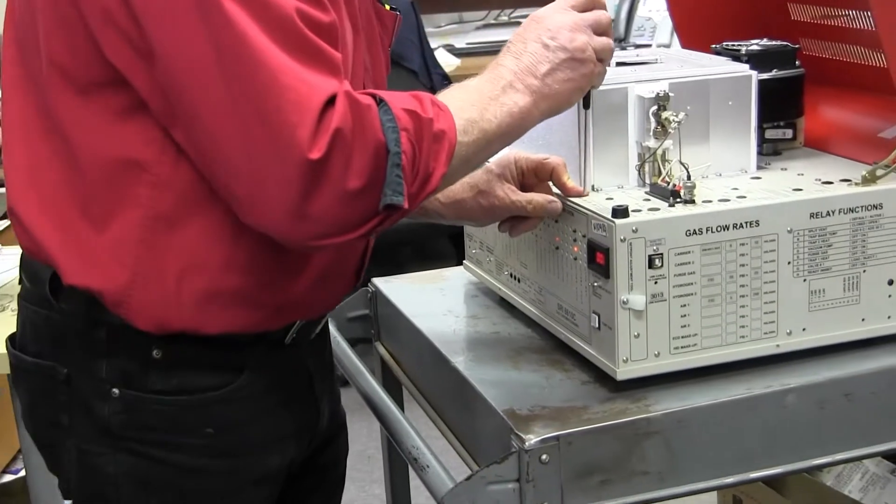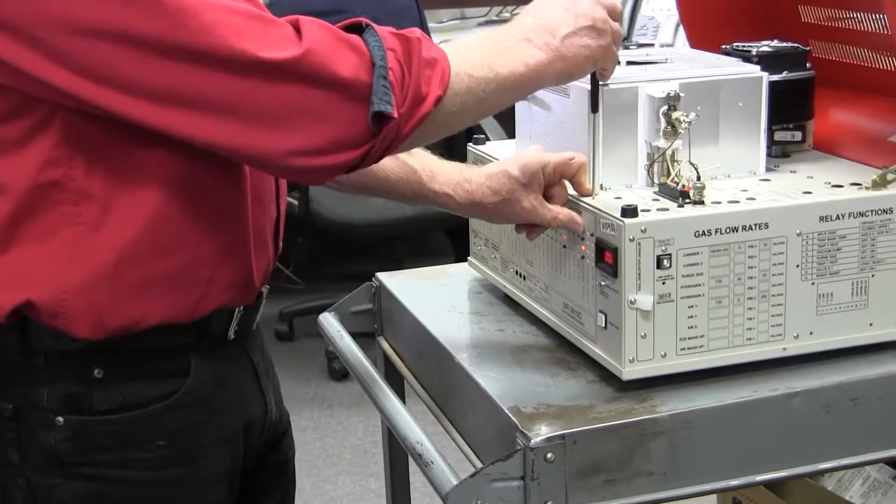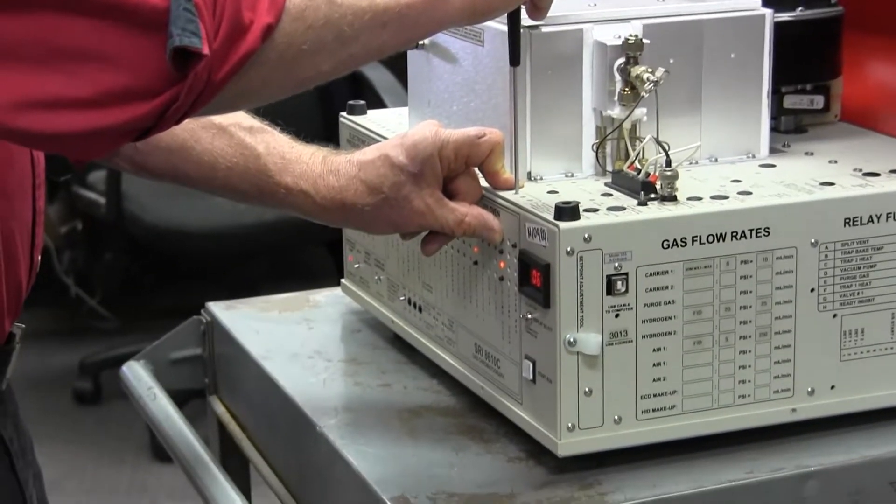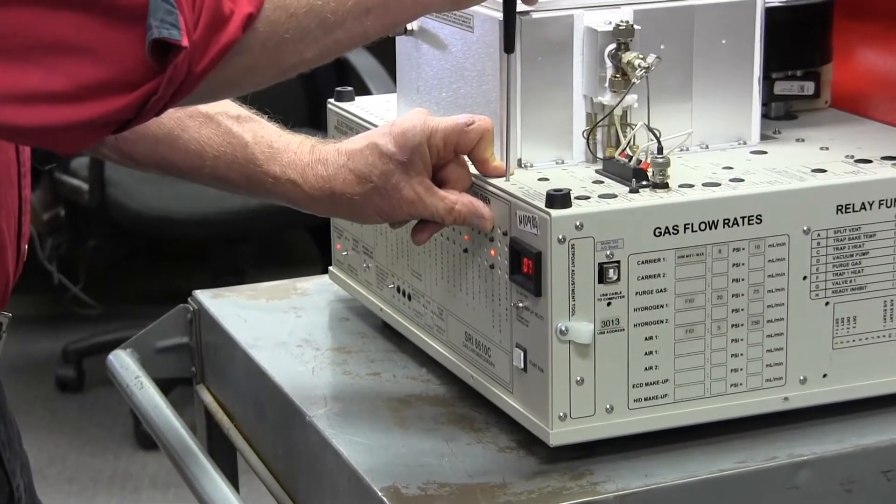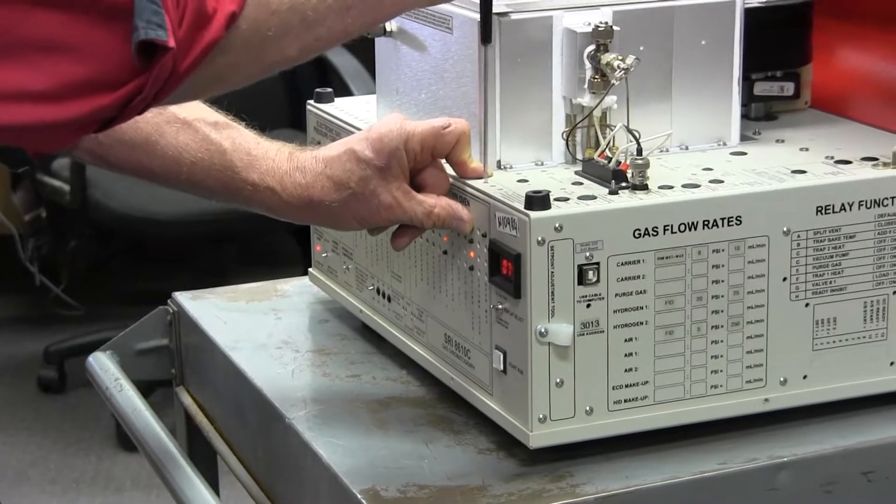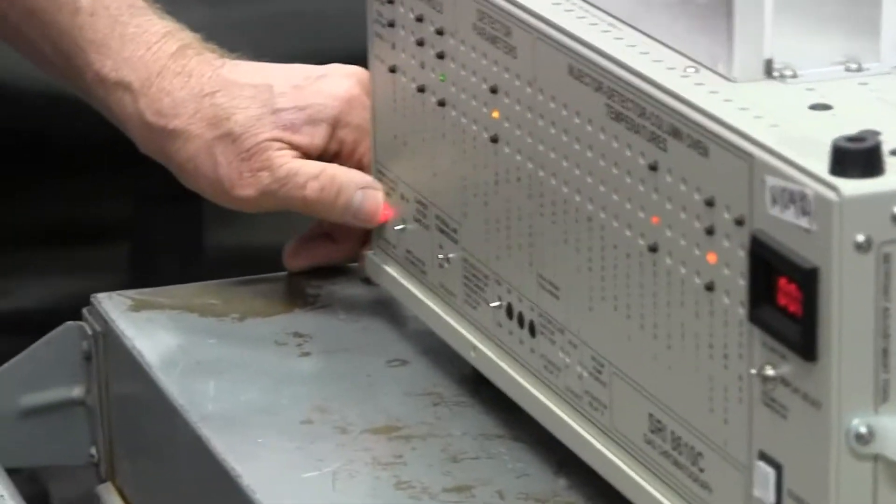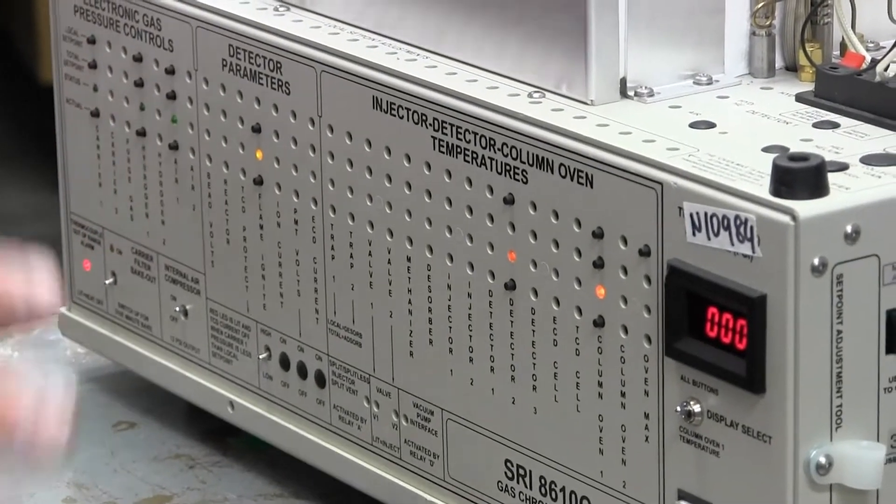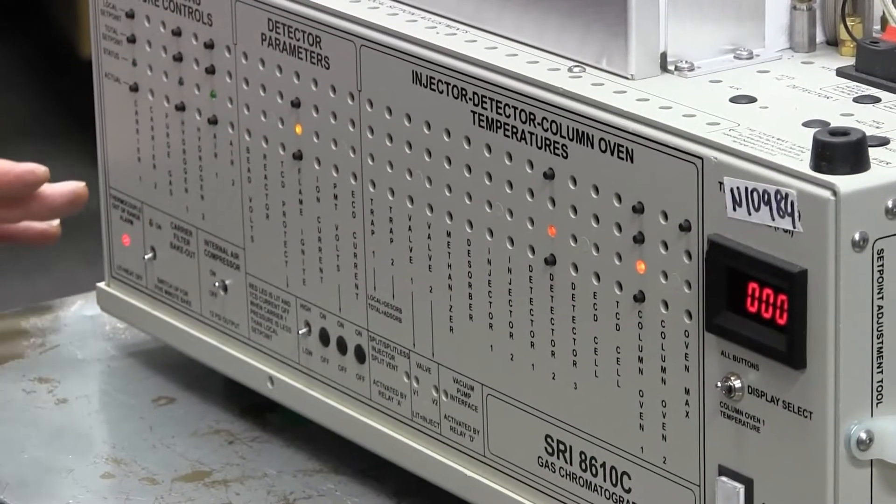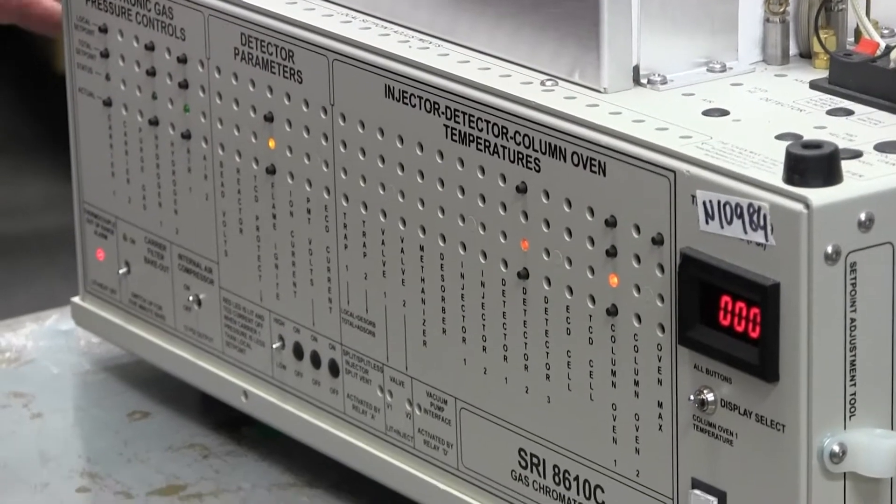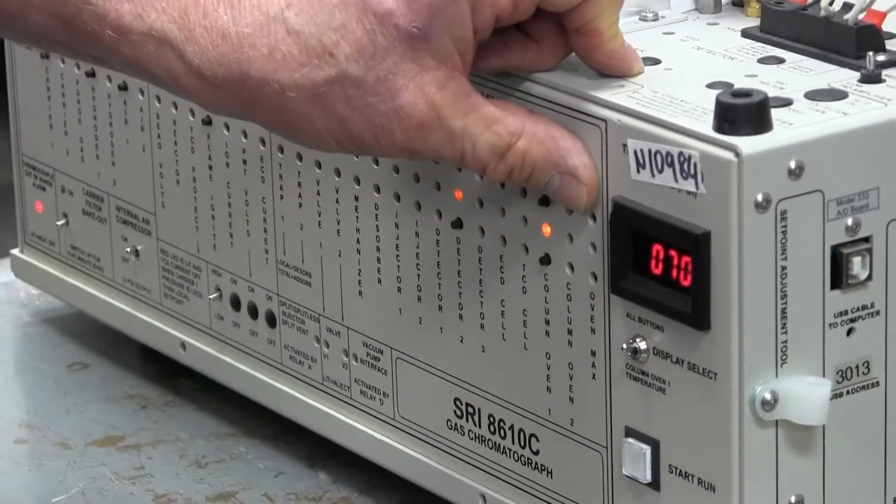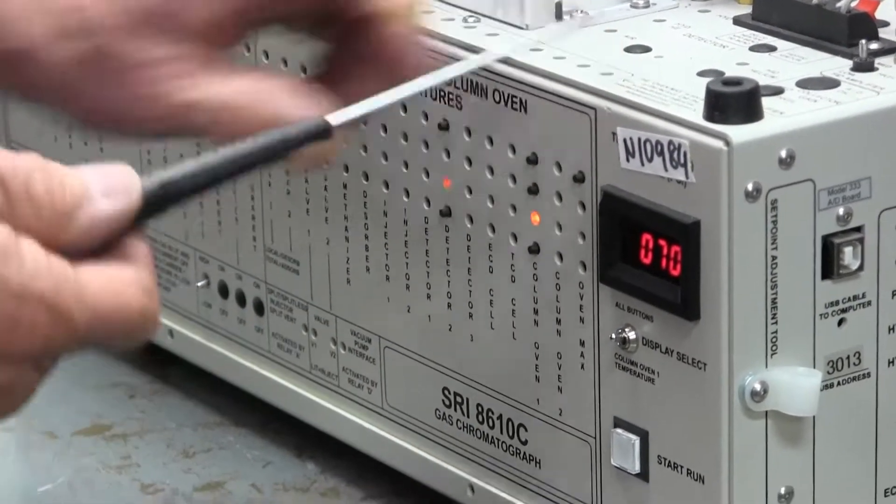So let's see if that happens. I'm going to turn the oven temperature up to, I'm getting very close to 70. Right there at 70. And now I'm a little higher than 70 and this thermocouple out-of-range lights. So what happens when this lights is that nothing on the GC is going to heat. So the most common reason is simply that you set the oven temperature hotter than whatever the oven maximum is limiting it to.